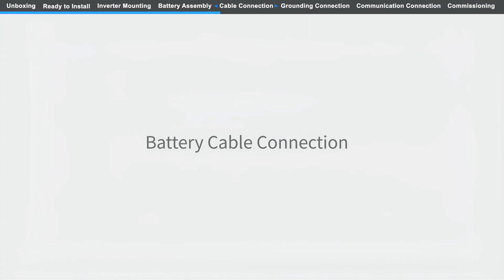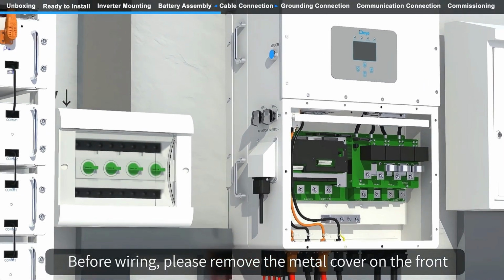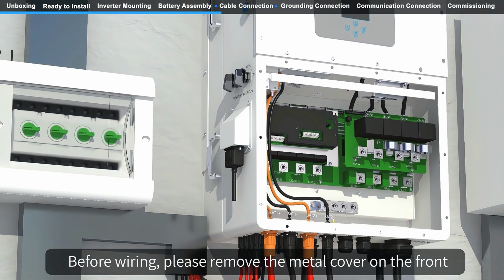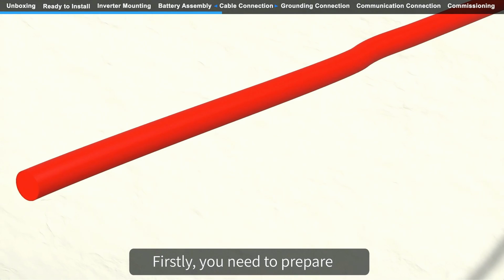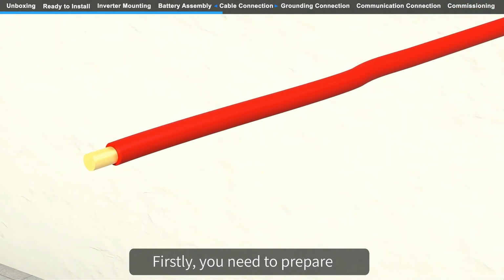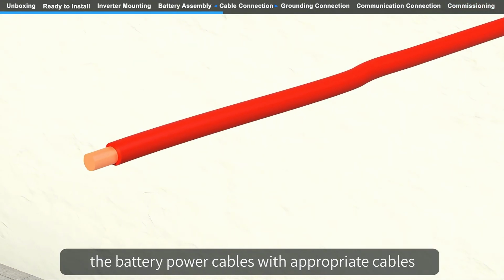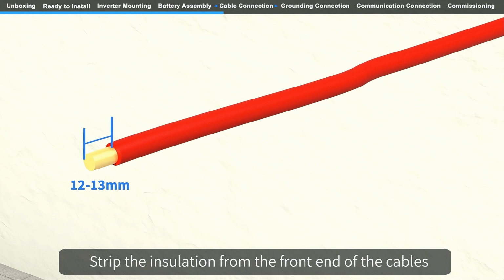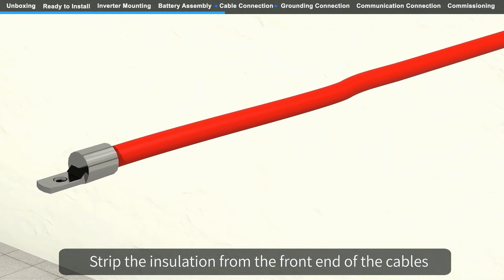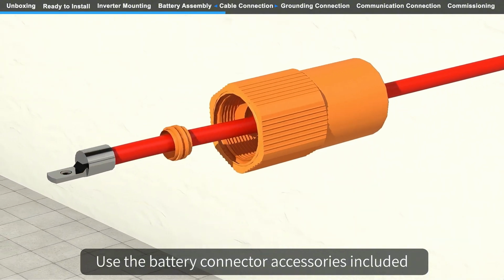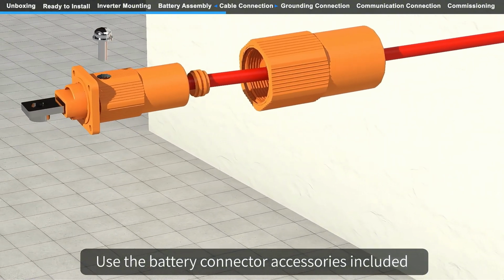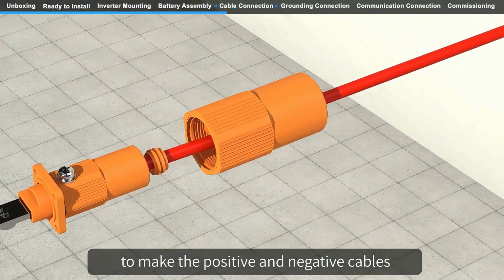Battery cable connection. Before wiring, please remove the metal cover on the front. Firstly, you need to prepare the battery power cables with appropriate cables. Strip the insulation from the front end of the cables. Use the battery connector accessories included to make the positive and negative cables.